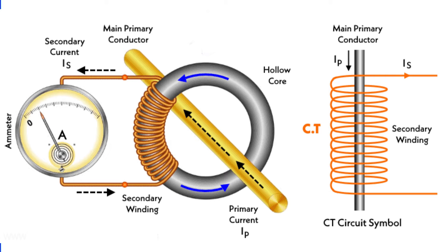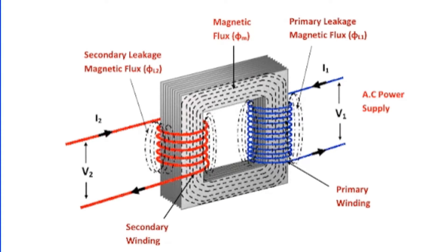But if we consider a situation where the secondary winding of a CT is left open, the circumstances change drastically. In such a scenario, the secondary current will effectively become zero, while the primary current maintains its original value. The result is an imbalance in the system. This imbalance creates a significant net magnetizing MMF, which is concentrated in the core of the CT, launching a considerable amount of flux into the core.